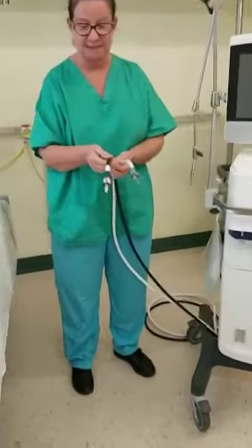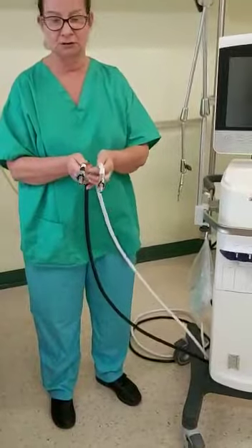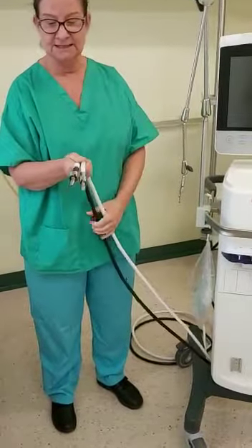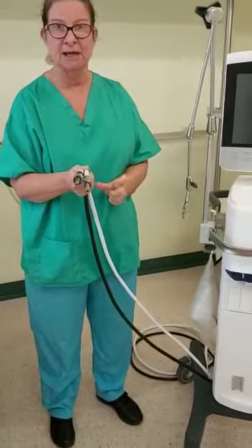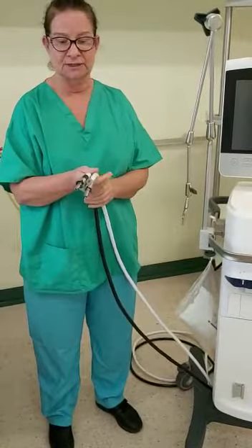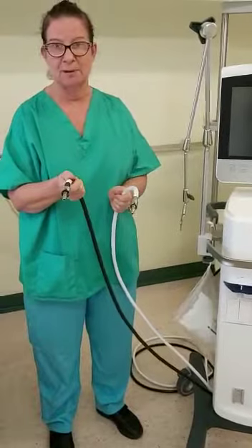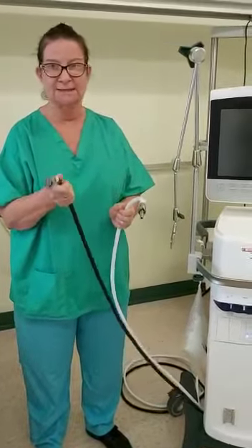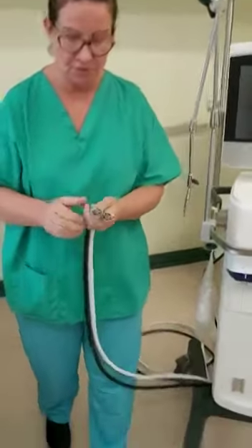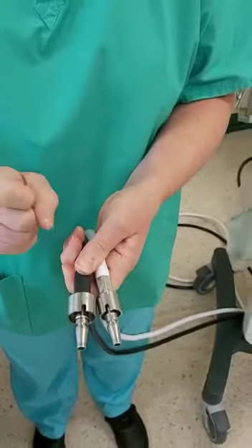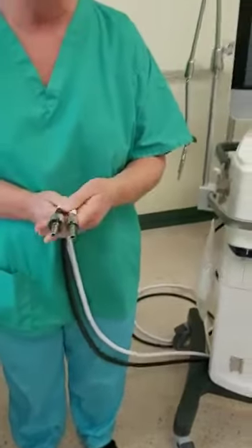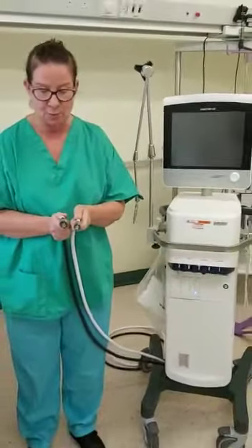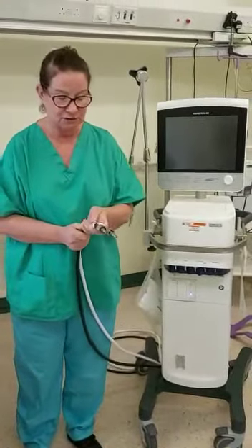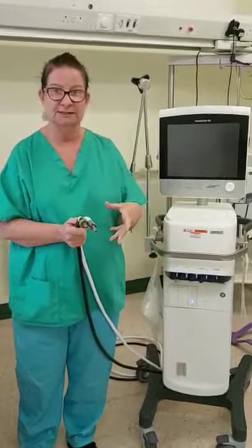Your air hose is the black hose and your white hose is your oxygen hose. And when we plug these into the mains gas supply, you'll see that they are colour coded. So white will go to white, black will go to black. So oxygen is white, air is black. On the top, where you plug it into the main supply, you can see you've got a little notch in the metal part, and that needs to be lined up onto your main supply when you insert the hoses. So we'll just demonstrate now how to insert the hoses into the mains gas supply.